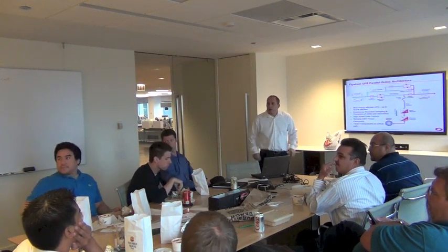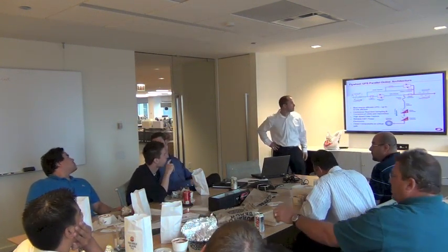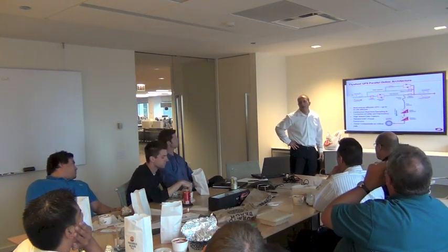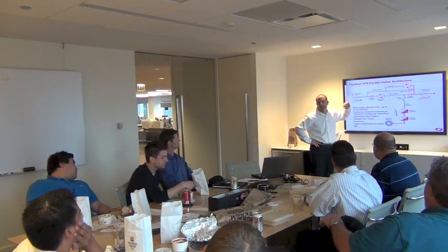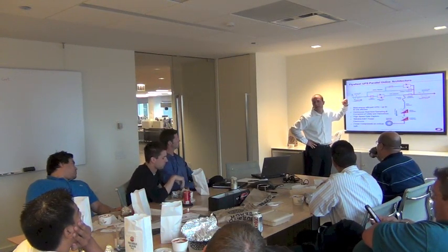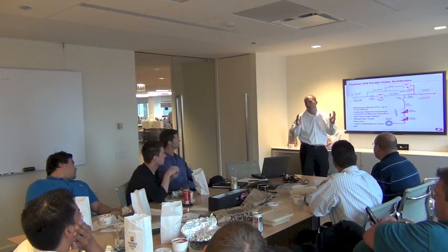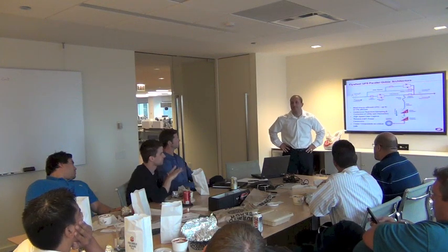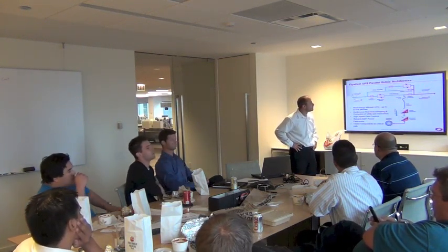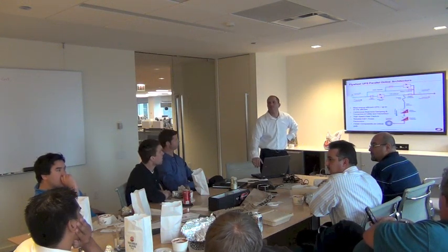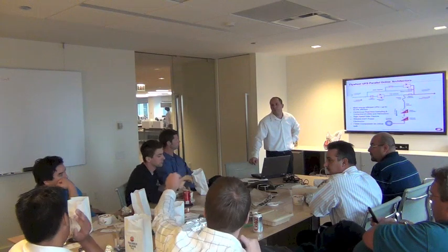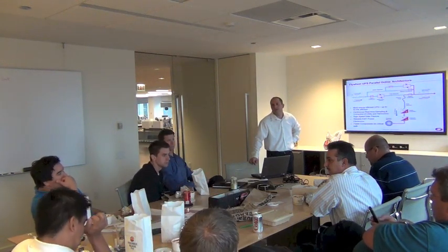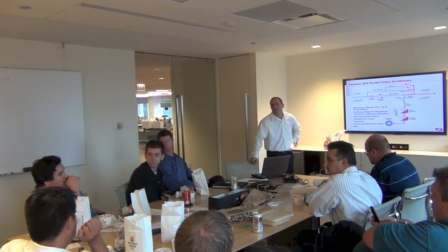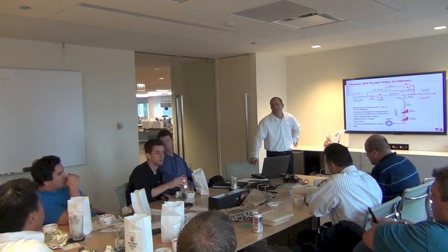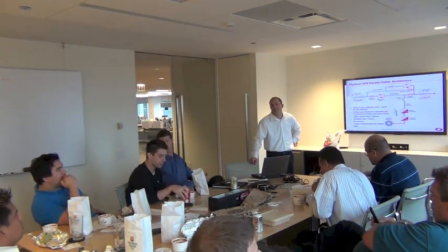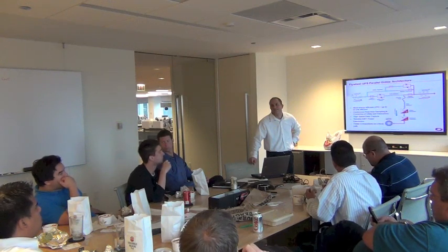Can you tell me if your bypass output is synchronized if you used a dual input source? Yeah, if this was a dual input UPS, it has to be synchronized. It cannot be from two different sources. If it's coming from two different utilities, normally we get it from the same panel, but it definitely has to be synchronized. Which is a common problem with all online UPS. Some manufacturers have come back and said, our static switch acts as a device that as long as both sources are available, we'll cut the static switch in when the sine wave is in the right phase angle, and you won't see any change there. I'm not quite sure that works as well as they claim to.